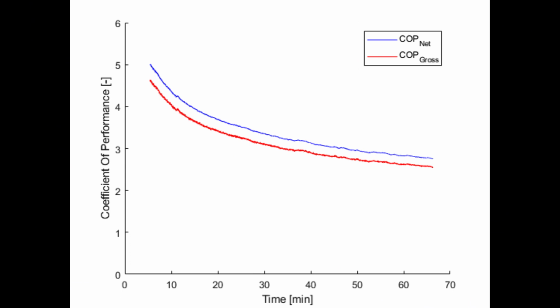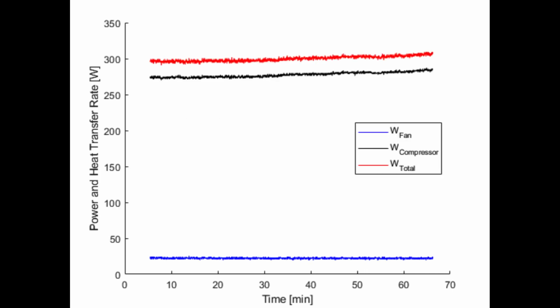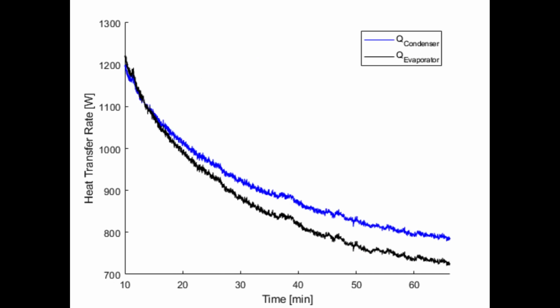After performing tests on the heat pump system, we found the net coefficient of performance to range from around 3 to 5 over the entire runtime. This net COP value means that we output 3 to 5 times as much heat in the water than the power consumed by the compressor. For our system, the compressor ran just under 300 watts throughout the operation, while the evaporator and condenser were transferring heat anywhere from 800 to 1400 watts.